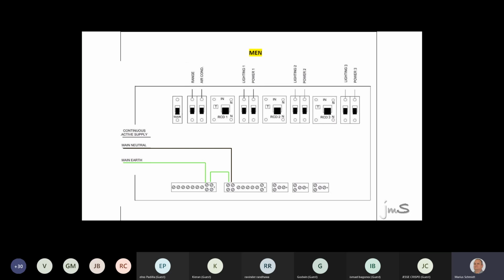It's not there. It says you must identify it. Doesn't say how. But how do I identify it there? Have a look at the amount of screws. 2 screws. So now, another way of identifying it. Where do we put a tag? You put a tag on the peg if the earth can be disconnected with a clamp. If it's Cadwelded, then you don't have to put a tag as well. But guys, Marius always says, be safe, be kind. Put a tag there regardless, and you will always be good.